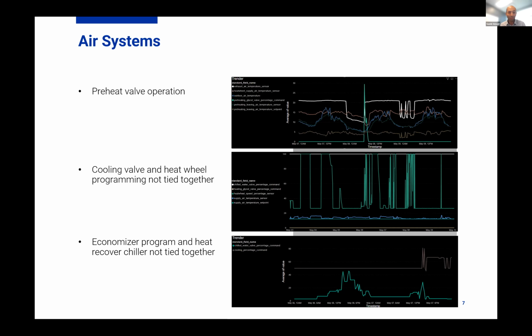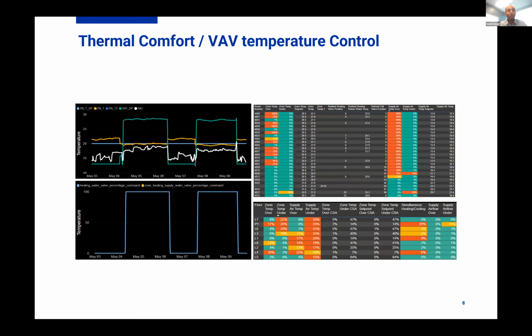And this last one is also tied into the same point: the economizer operation, kind of the basic points of commissioning, wasn't properly set up with our heat recovery chiller. So it wasn't set up to give us as much heat extraction as possible. So kind of the opposite issue as our second point. And we found these issues, and I kind of assumed these would be the basic parts of what we could have found out during our air systems, but I was surprised, because when we went deeper into our floor operation, we quickly realized that there are major issues.